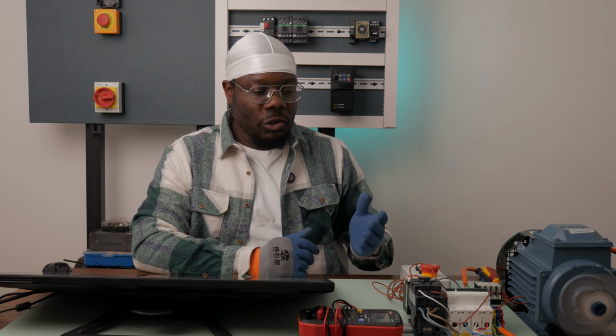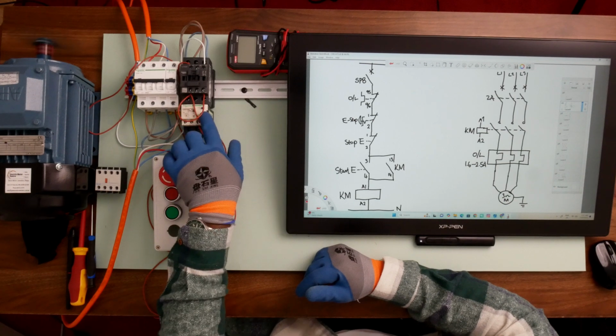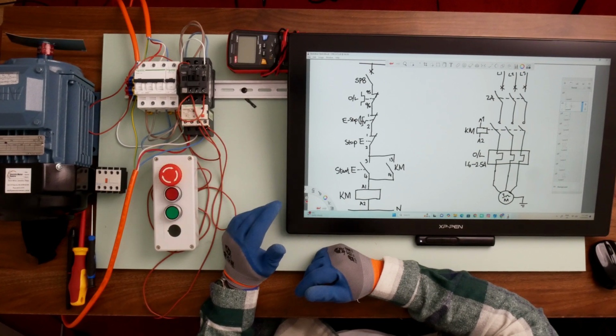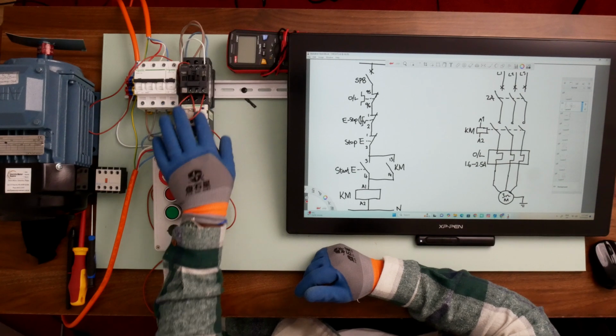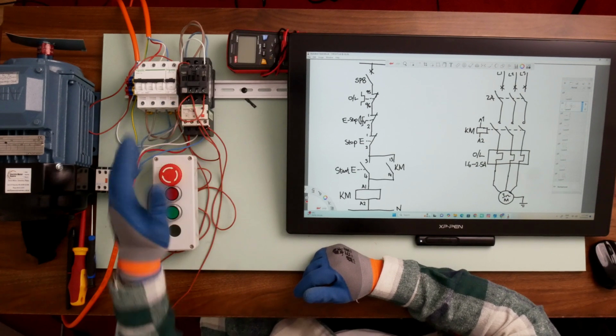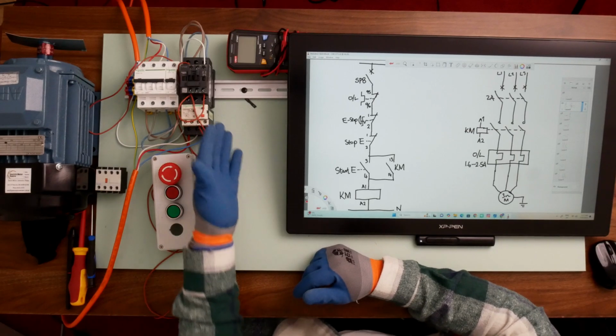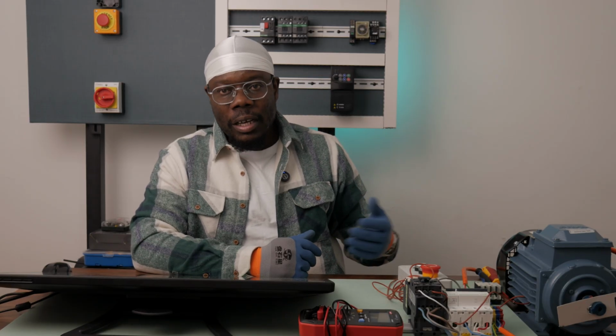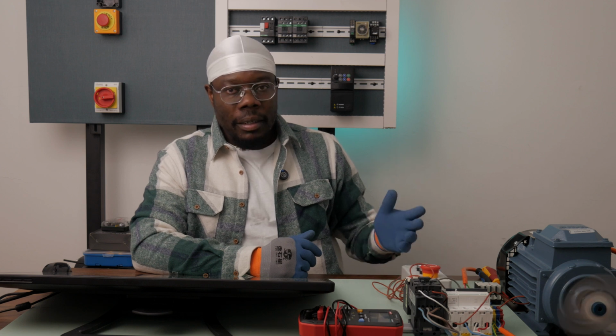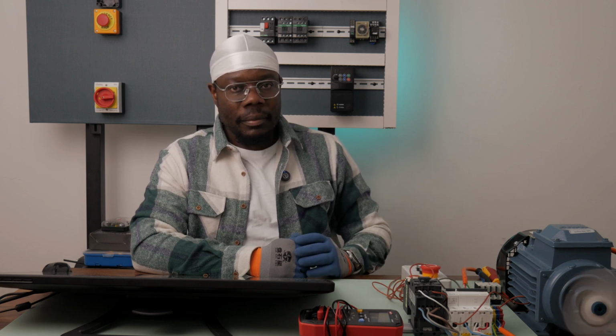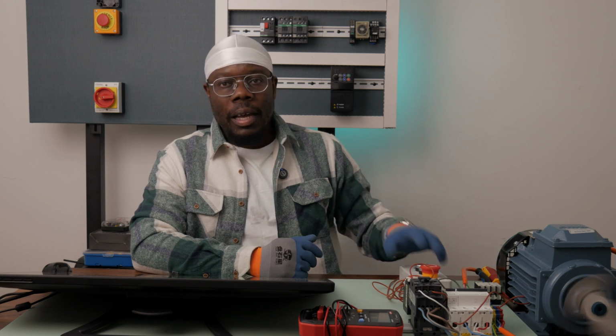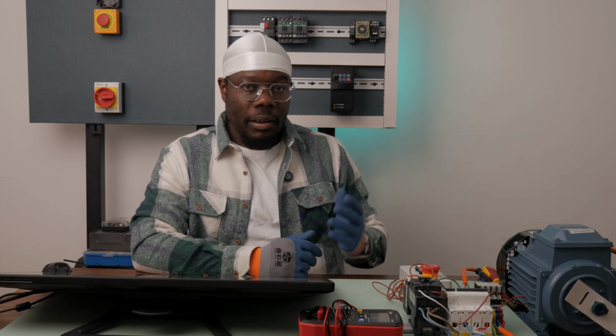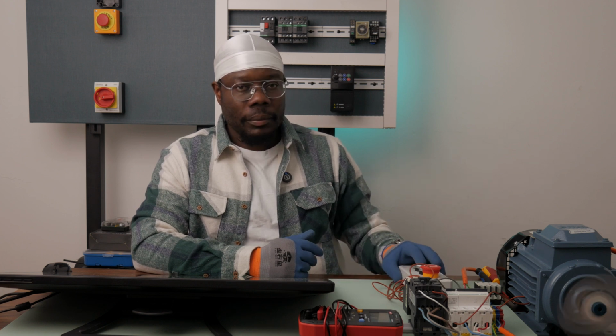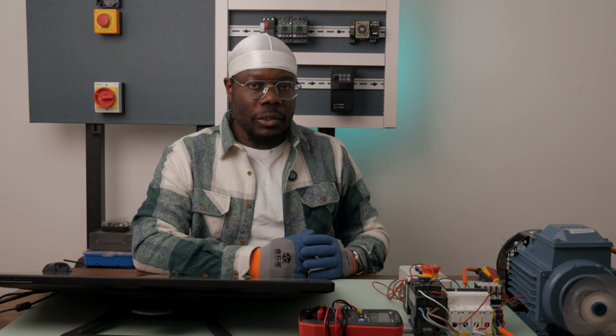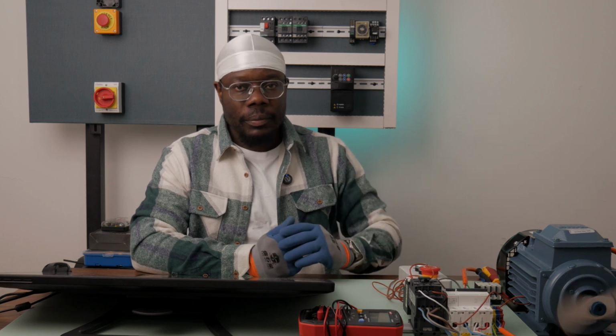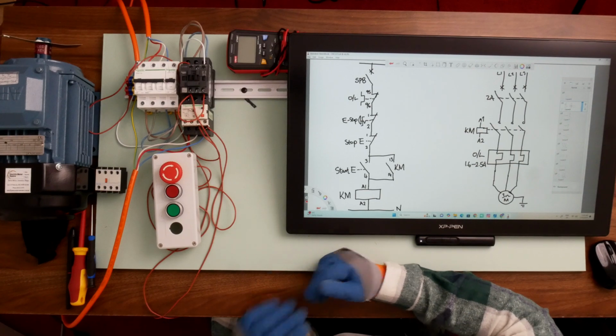And now we can simulate a trip on the overload and see if it stops. See? Now we have to reset the overload. Now let's start it again. So we've reset the overload, but the motor doesn't restart on its own. So we've done the right thing. Started it again. And our stop works. Now let's run it for the last time. And let's check our e-stop if it works.